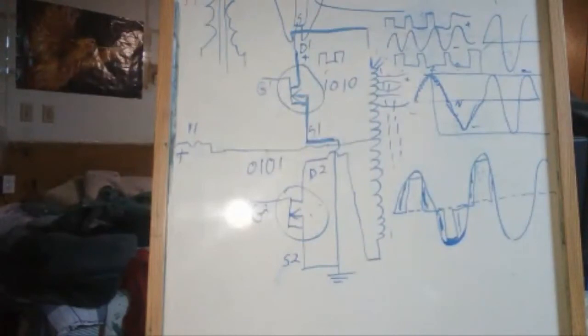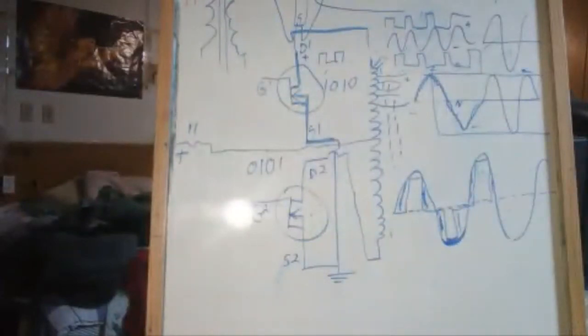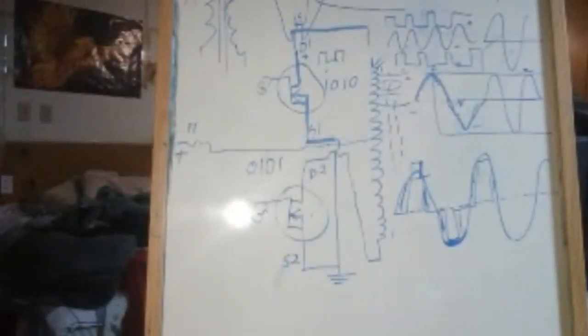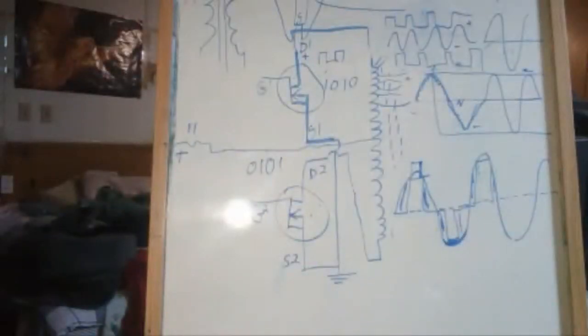So if you have a certain load on a modified sine wave, you'll get a lot of ringing. If it's like a transformer, you'll hear it really badly, and the voltage can even spike out of the active linearity region of the sine wave that's supposed to be generated. It's supposed to output 120 volts RMS, right? Well, sometimes it can jump as high as 150 to 160. That's not really good.